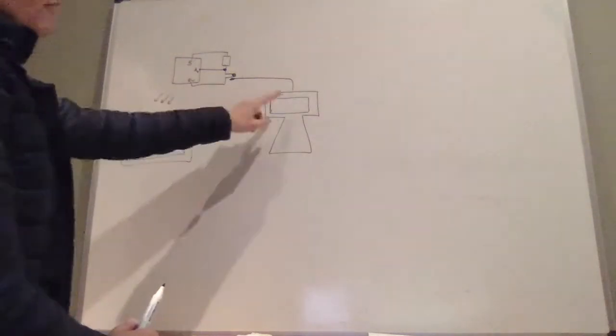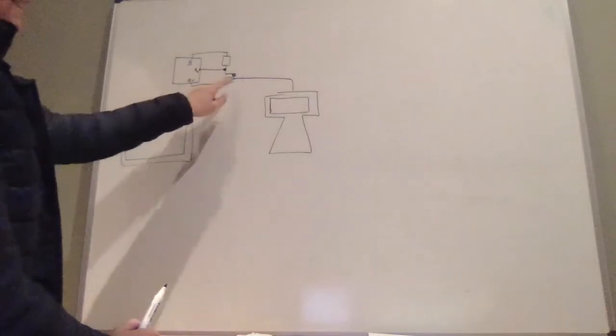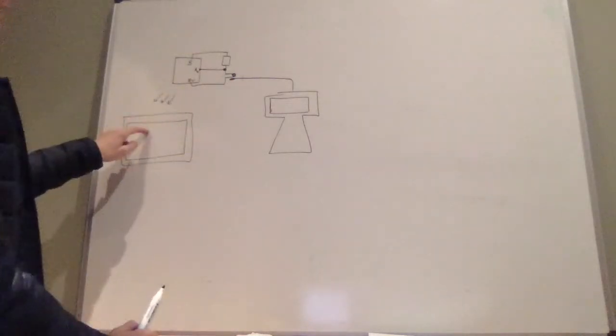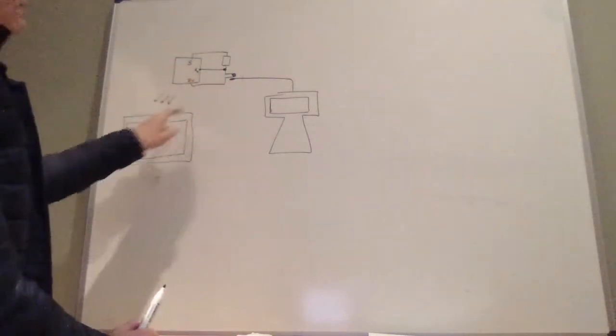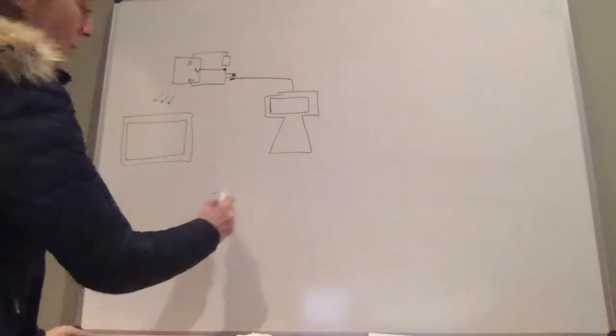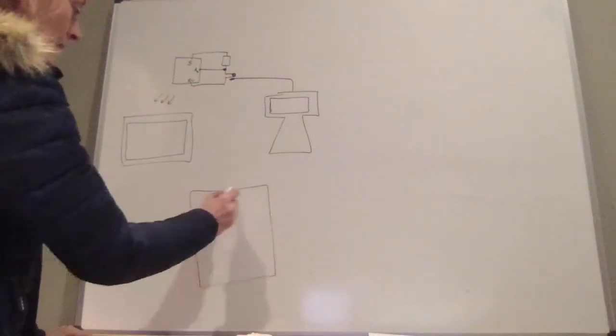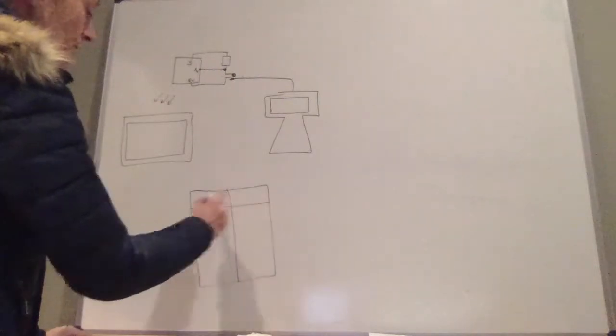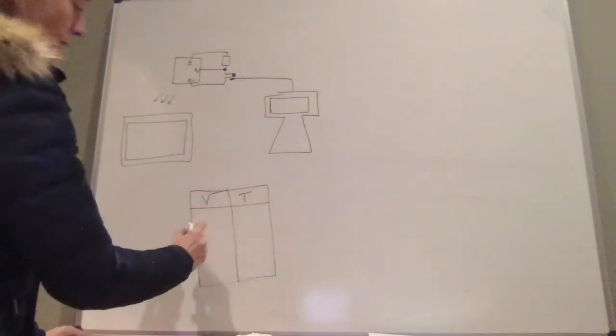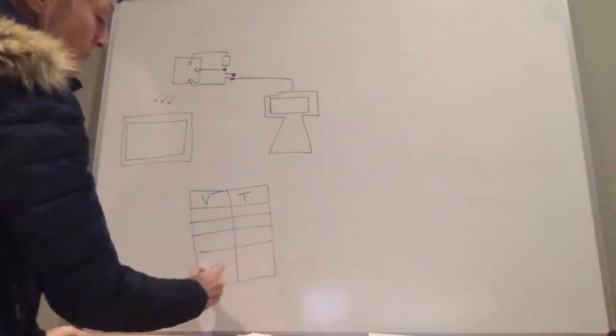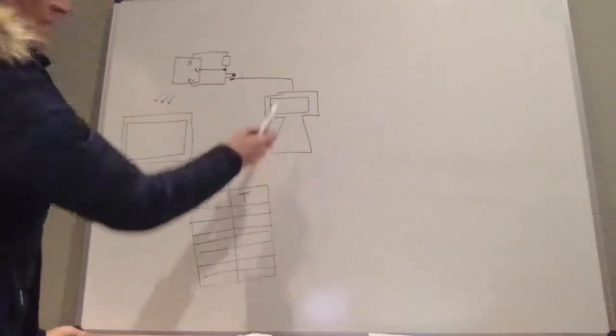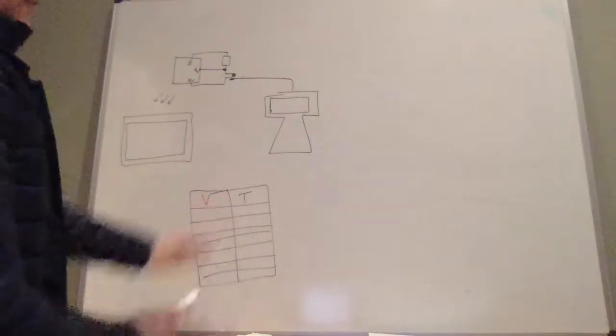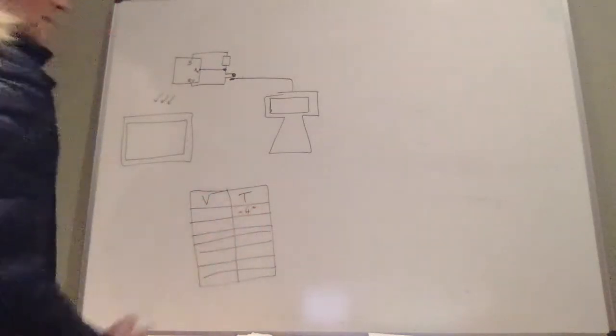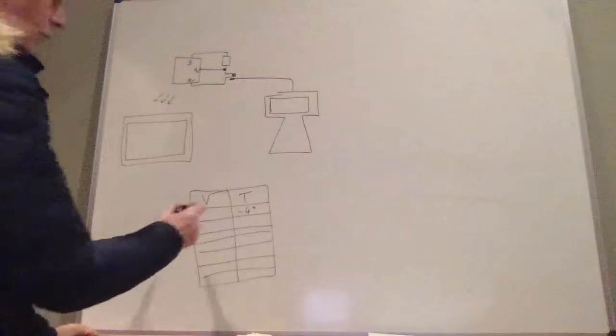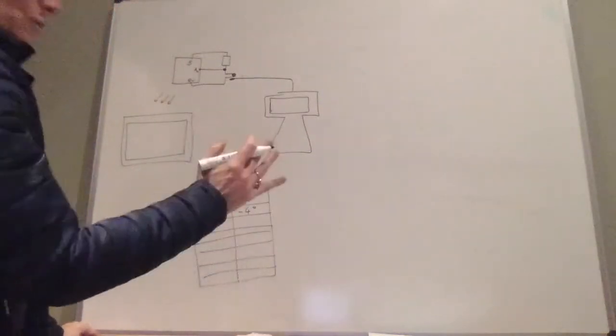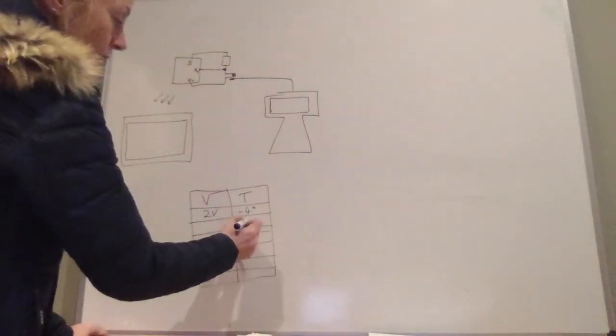Because now you have a reading on the data logger that represents temperature, and you have a reading on the screen that represents the voltage that corresponds to that temperature. So you need a person here with a piece of paper, and they are going to record voltage and temperature. So they're going to write it down, okay? This person will shout out maybe a reading for the temperature, maybe -4 degrees. This person will shout out a corresponding voltage. It might be, I'm making this up completely, 2 volts. This person might then say 0 degrees.